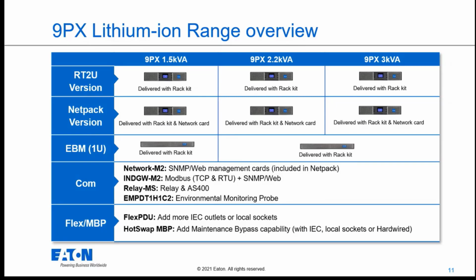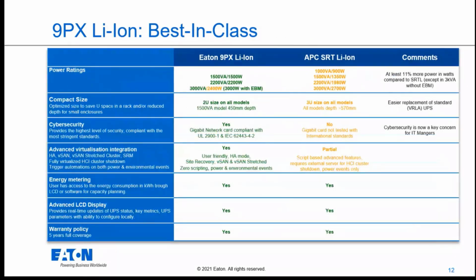And we have, of course, the famous hot swap MBPs for maintenance bypass capabilities on the UPS, or manual maintenance bypass capabilities. They are available either with IEC connectors, local sockets, and we also have a hardwired version for people willing to hardwire the UPS. This is very similar to what you know from the 9PX range.